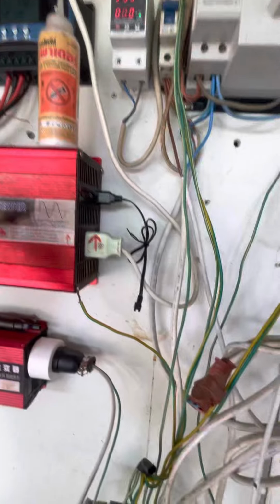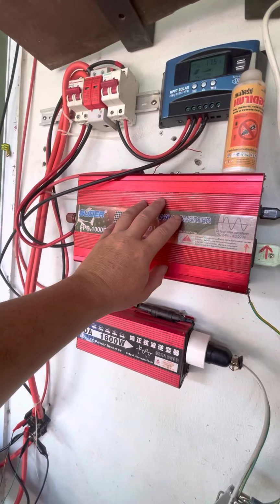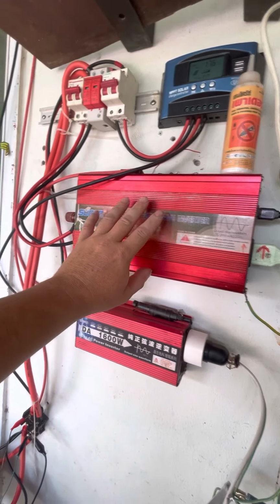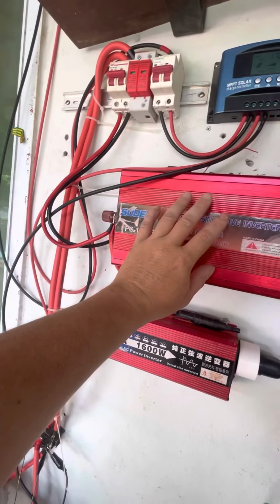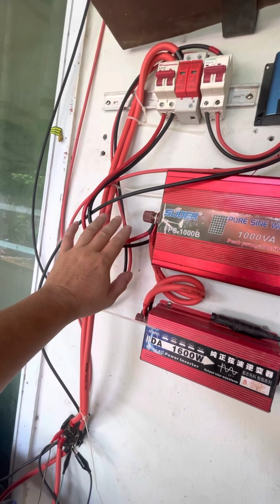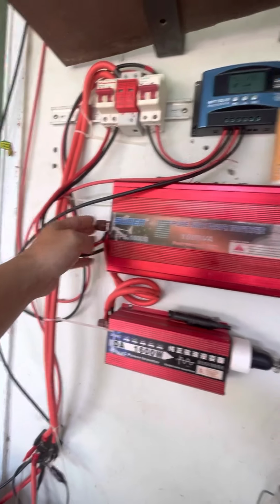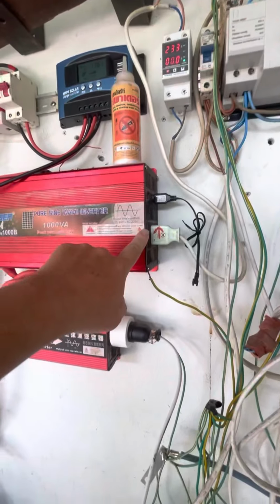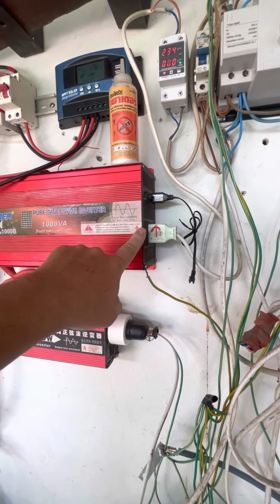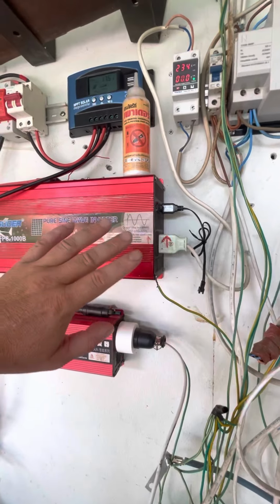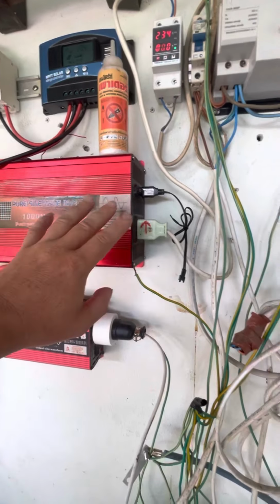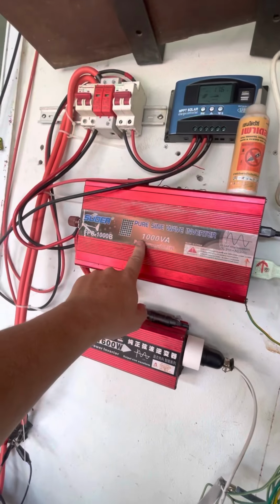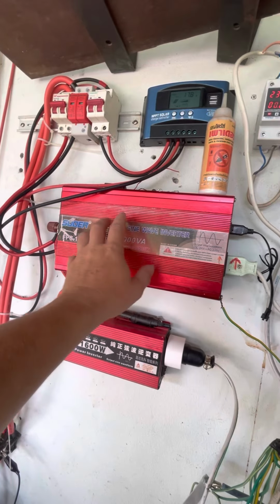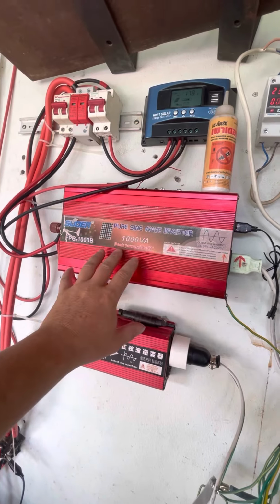And these are just joined together off of the common battery pack. I thought, that's weird. What happens with these is, I think I might have said before, the control protection only looks at what's coming in, it doesn't care what's going out. And this lot can go down to like 170 volts. Your stuff just has to suffer, it doesn't switch off. That's if you overload this - say you take out 1500, it won't shut down, it'll just lower the voltage.